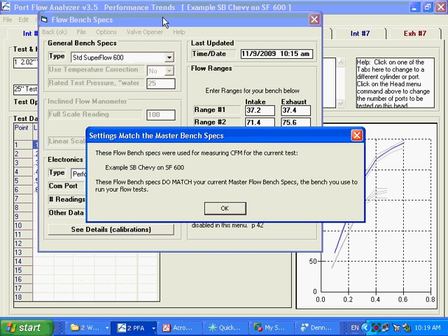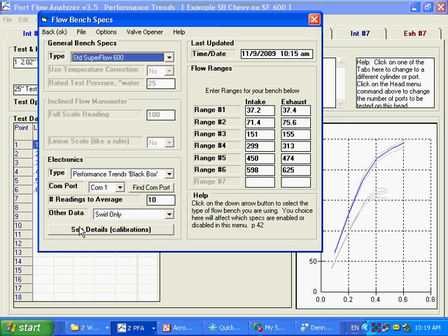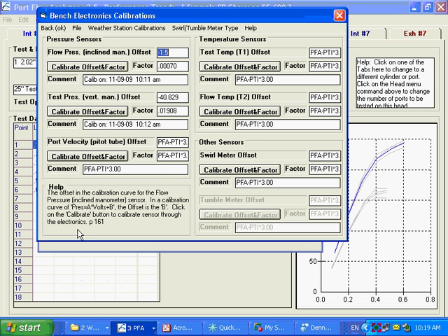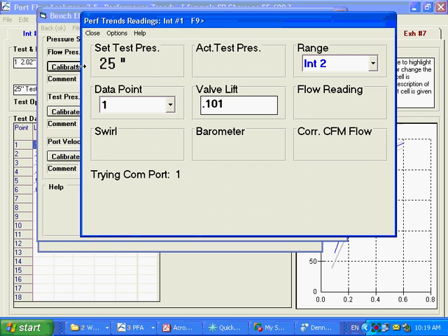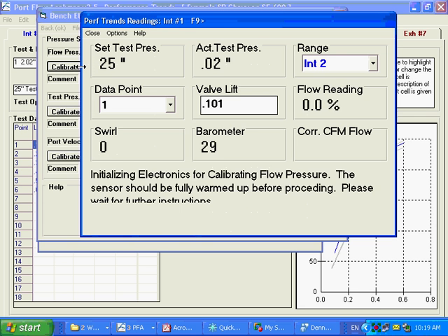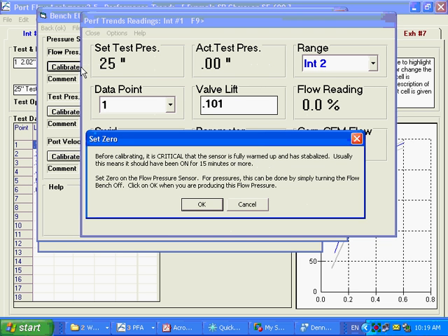We're going to go into flow bench specs. We're going to go down into see details, and we're going to do an actual detailed calibration. We're going to do the incline manometer first by clicking on this button. And you see this little instruction screen come up. Before calibrating, it's critical the sensor is fully warmed up. That means that the black box has been on for 15 minutes or more. And then it says set zero pressure.